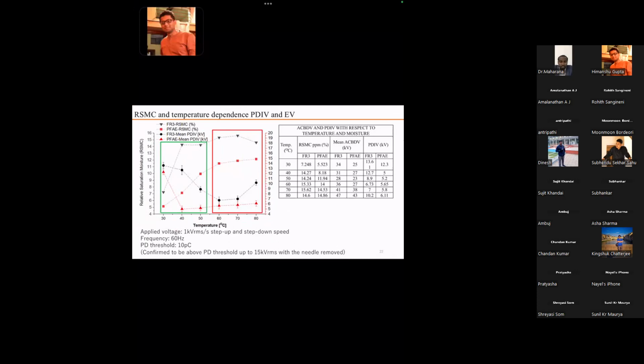I'll show you that. Here also there is a reverse phenomenon we have observed. We studied the relative saturation moisture content with respect to partial discharge inception voltage, and observed that as the relative saturation moisture content increases up to 50 degrees, the partial discharge value decreases, and beyond 50 degrees it is almost stable, with some deviation around 80 degrees. Because of this difference in behavior, we have studied the mechanism behind it. We need to analyze the chemical formulation and the chemical things involved here.